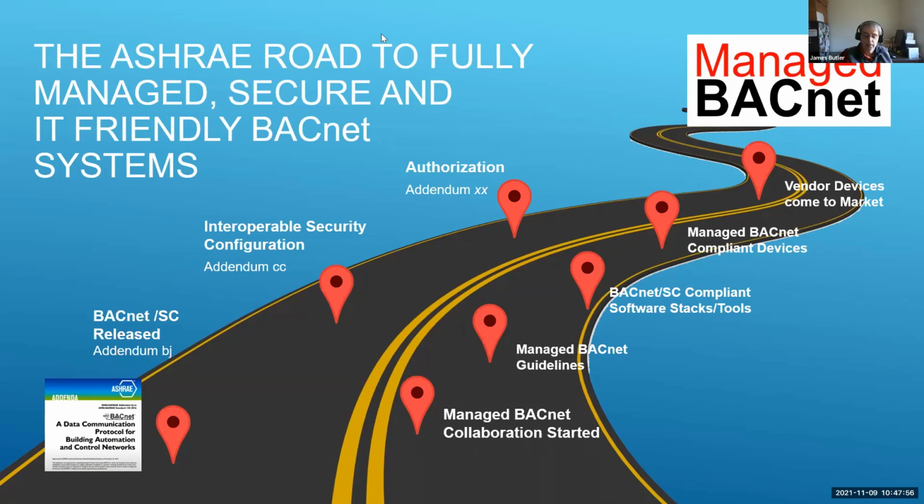BACNET IP, you could say, well, that's using IP networks, which of course is true, but BACNET IP was never intended to use digital certificates. So at least for now, digital certificates will only be used with BACNET Secure Connect devices, which makes the problem of managing them a little bit easier, I suppose.